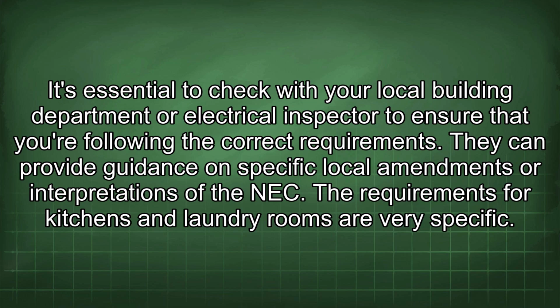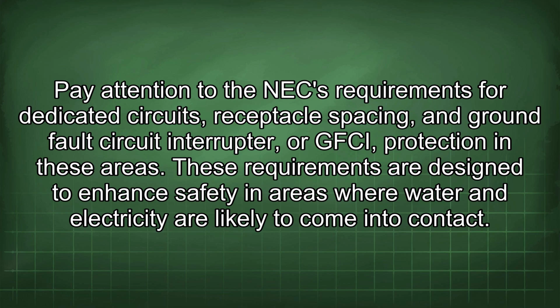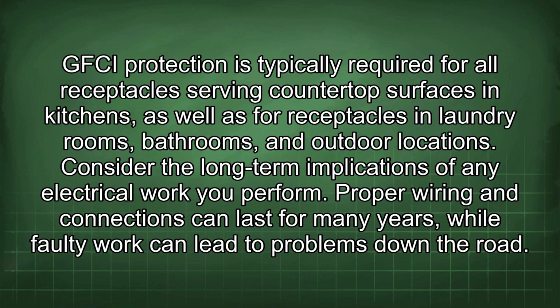The requirements for kitchens and laundry rooms are very specific. Pay attention to the NEC requirements for dedicated circuits, receptacle spacing, and ground fault circuit interrupter, or GFCI, protection in these areas. These requirements are designed to enhance safety in areas where water and electricity are likely to come into contact. GFCI protection is typically required for all receptacles serving countertop surfaces in kitchens, as well as for receptacles in laundry rooms, bathrooms, and outdoor locations.